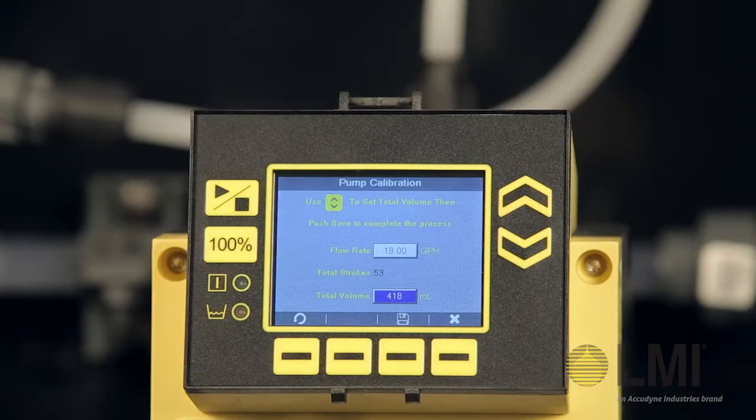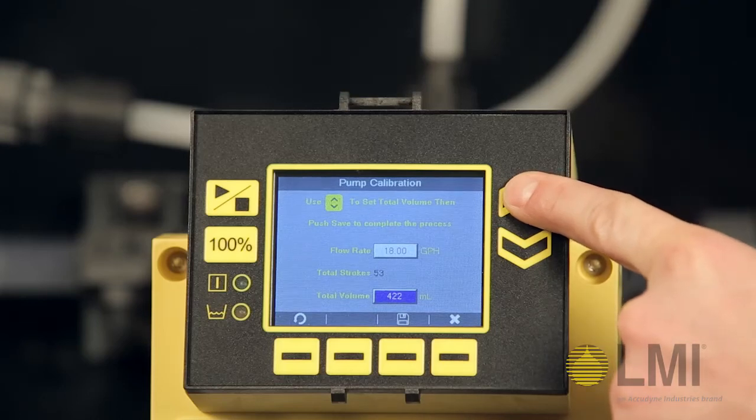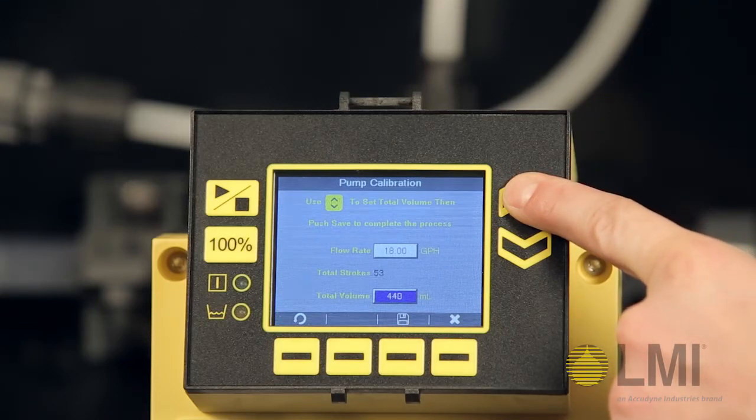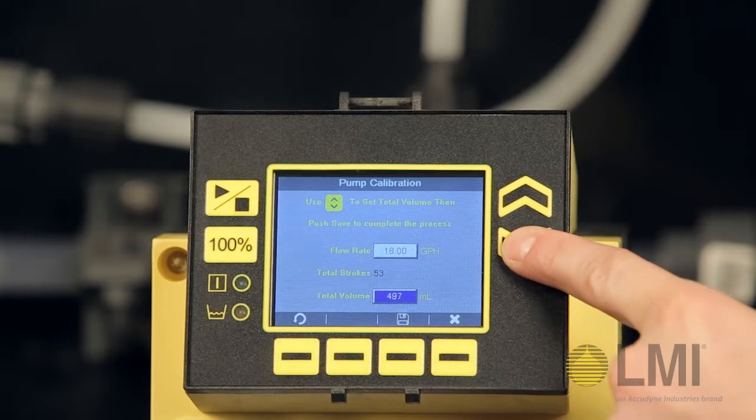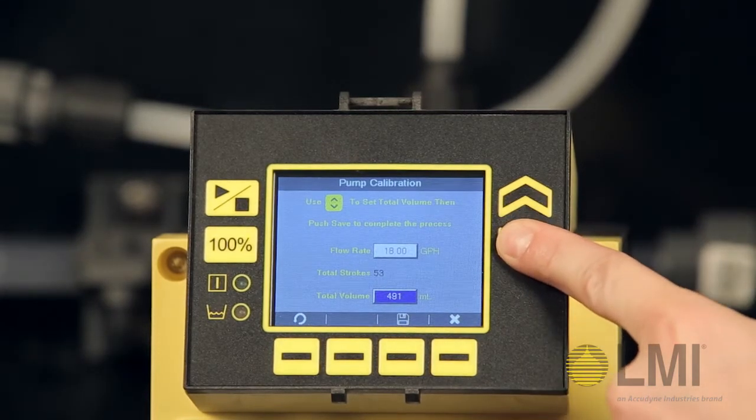We will need to adjust the total volume field area using the up-down arrow buttons on the right side of the display to match the fluid amount drawn down from the calibration cylinder. In our example, we are adjusting to 490 milliliters.